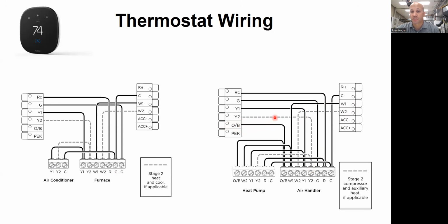But this is my reversing valve wire. The thermostat has to tell the reversing valve to switch between heating and cooling. So when it turns on Y, that Y gets piggybacked to the outdoor unit, Y1 in this case, and that would turn on the compressor. Do I want the compressor to run with the reversing valve ready for cooling, or do I want the compressor to run with the reversing valve ready for heating?